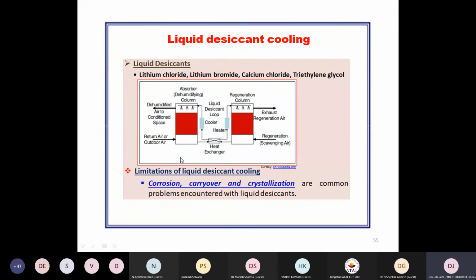The material may be a liquid desiccant such as lithium chloride, lithium bromide, calcium chloride, or triethylene glycol. So there may be a compartment called the absorber column as well. A regeneration column is used. Room air may pass through the flow channel of the absorber. The downfalling desiccant in liquid state takes moisture out of the air and converts from a strong solution to a weak solution, and the dehumidified air is sent on for further cooling.